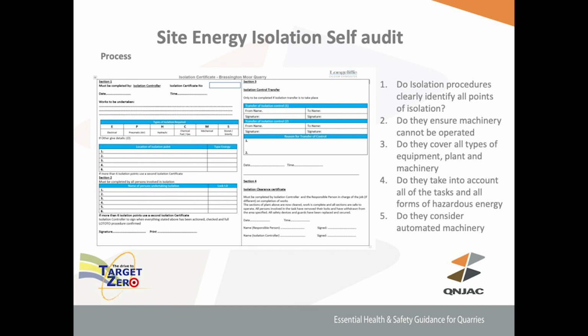Whilst they were trying to commission the controller, two fitters had already started changing some V-belts on another fan, but they'd fully isolated that fan, and fortunately weren't yet in the process of changing the belts. As they started up the plant, one of the fitters noticed the pulley on the fan had started to turn very slowly. They stopped the job, went downstairs, and spoke to the engineering and production supervisors. They then realised that starting the burner up had affected the airflows around the whole plant, and there was so much suction from the main fan that it had started to turn the fan these guys were working on.